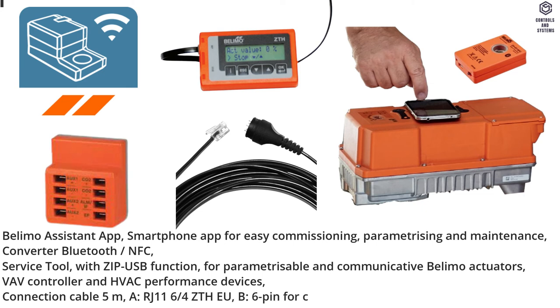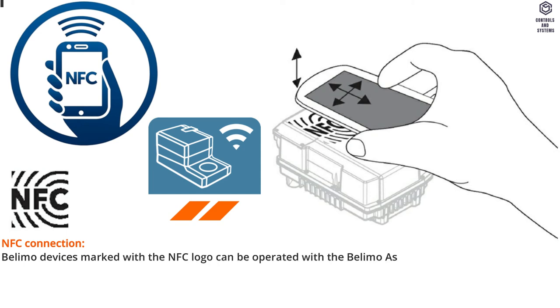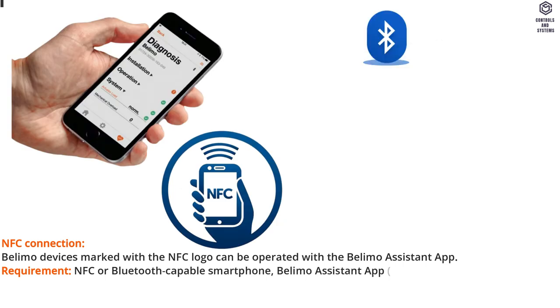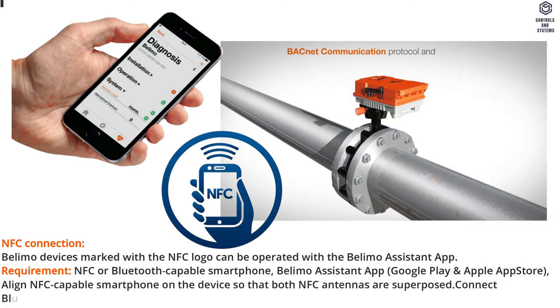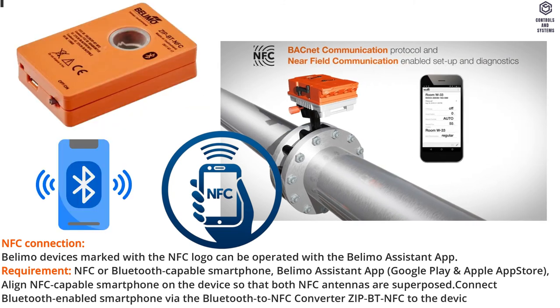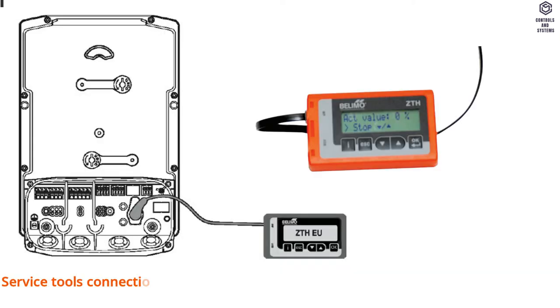Connection cable: A — RJ11 6/4 ZTH EU; B — 6 pin for connection to service socket. Service NFC connection: Belimo devices marked with the NFC logo can be operated with the Belimo Assistant app. Requirement: NFC or Bluetooth capable smartphone with Belimo Assistant app from Google Play and Apple App Store. Align NFC capable smartphone on the device so that both NFC antennas are superposed. Connect Bluetooth enabled smartphone via the Bluetooth to NFC converter ZIP-BT-NFC to the device.